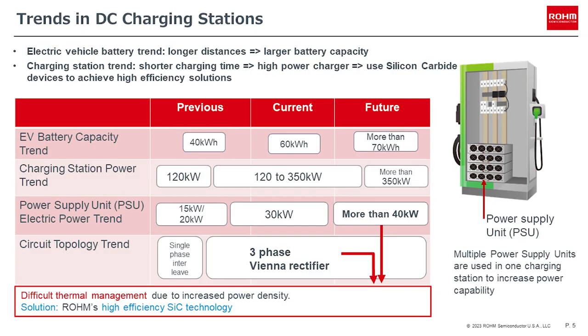The ever-increasing demand for EVs to drive longer distances on a single charge has steadily increased EV battery capacity over time. At the same time, the trend towards higher power DC fast charge stations has also increased. In order to meet the higher power demand, DC fast charging stations must contain multiple power supply units (PSU), as shown in the diagram above. Each PSU must provide more than 40 kilowatts of power in order to supply a total of more than 350 kilowatts. The circuit topology trend is to use a three-phase Vienna rectifier along with silicon carbide devices to provide a high-efficiency solution with better thermal management capability.